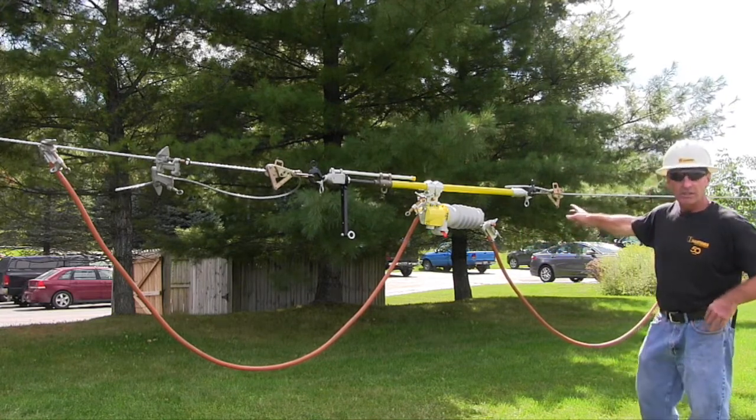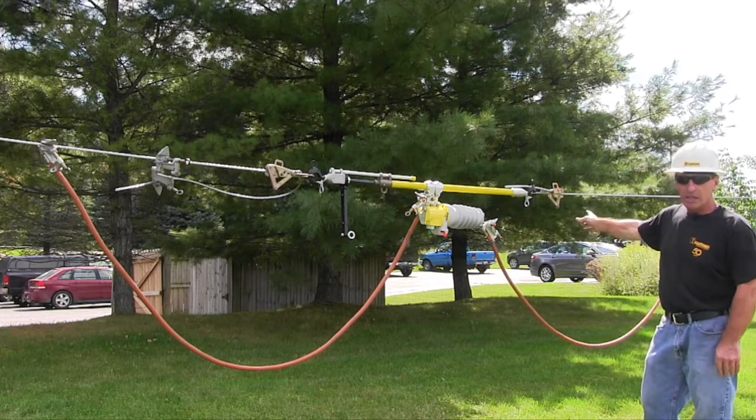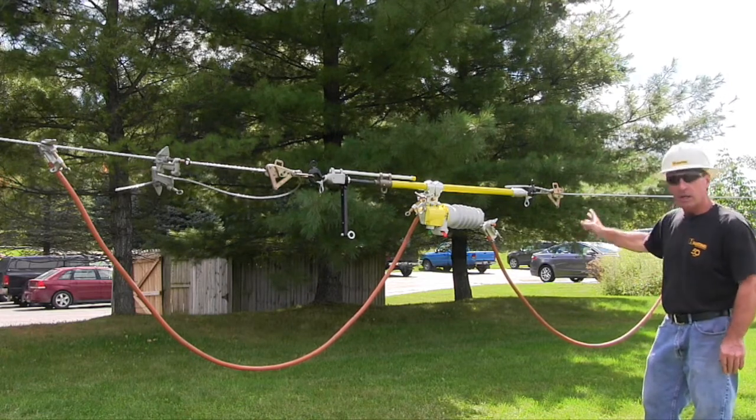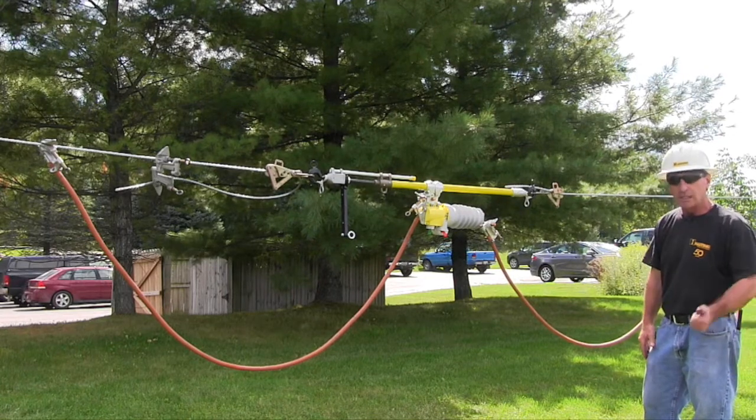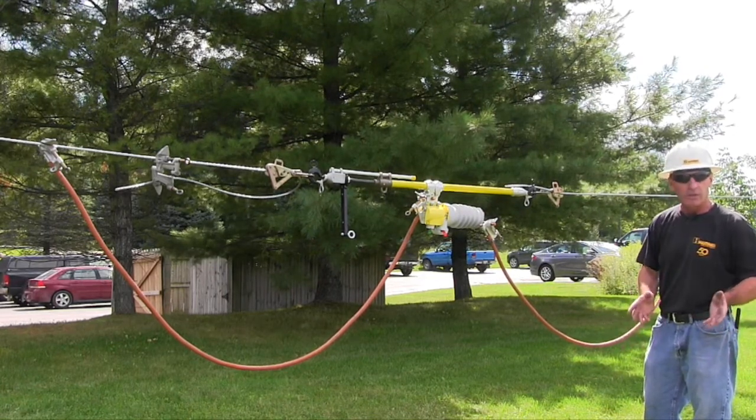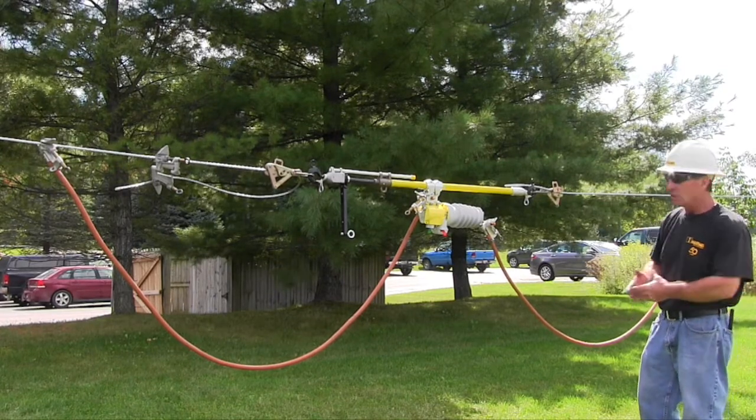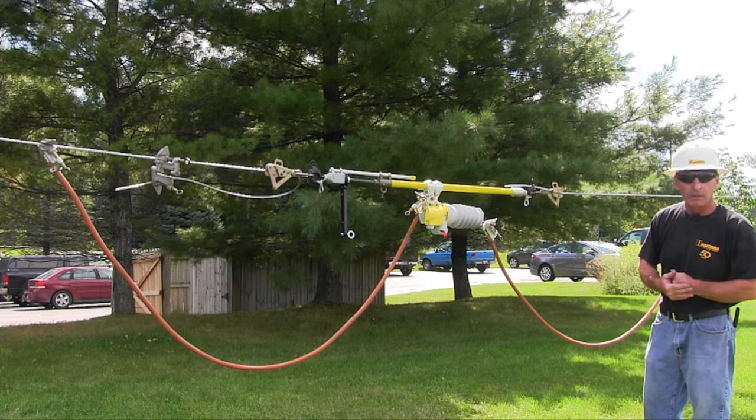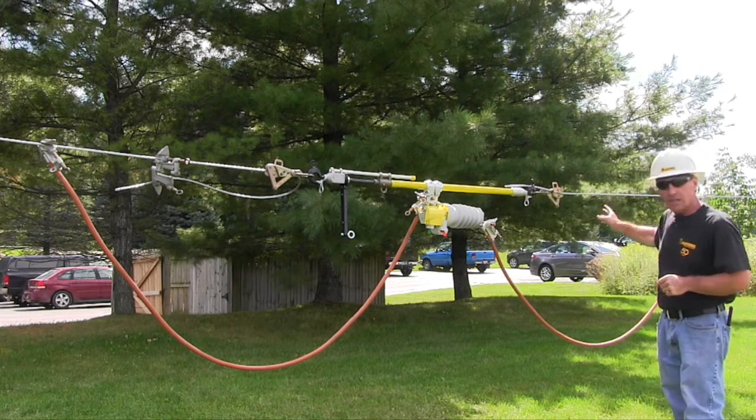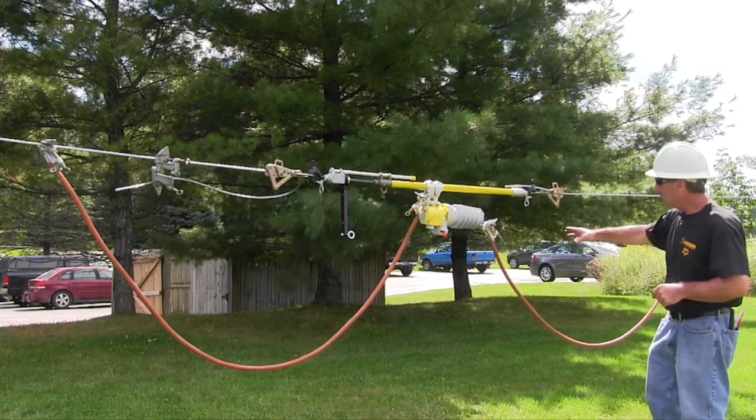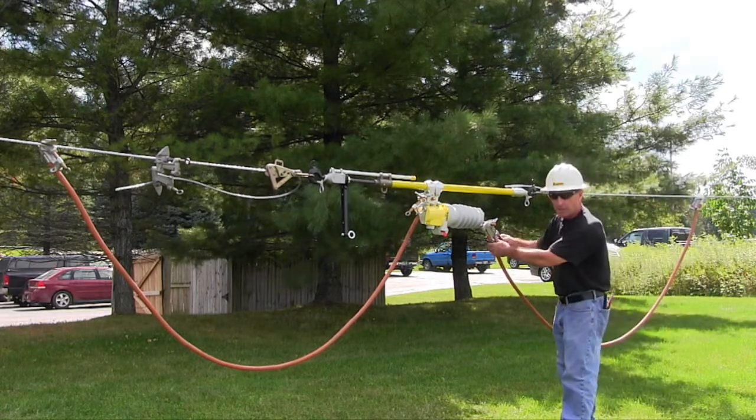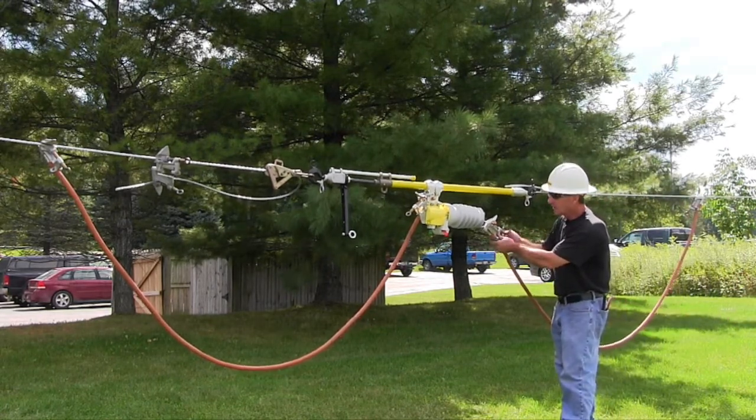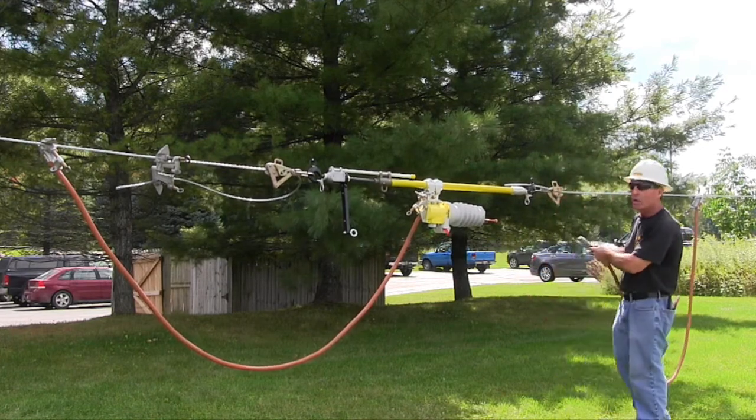Now that my switch is open, the next step would be to test for de-energized. I want to make sure that that is not energized before I go and hang my grounds on this other side. So I can take a proximity voltage detector like our 7701, or I can take the 6702 and I can make some volt measurements up here. Once I determine that this side is de-energized, I can go ahead and I can remove my jumper on the de-energized side and that's going to give me my visual opening.